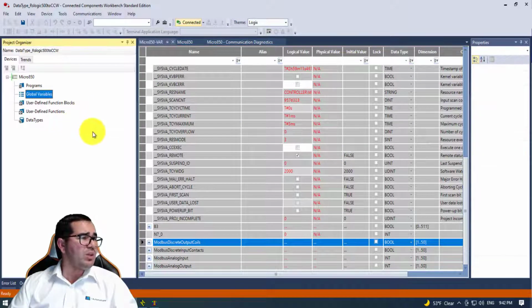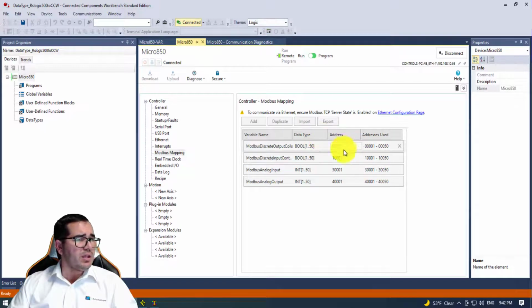After that, you need to make sure that you have these addresses. The output coils start on 00001 and go to 00050. Modbus discrete input contacts go between 10001 to 10050. Modbus analog input starts 30001 to 30050, and Modbus analog output goes from 40001 to 40050.